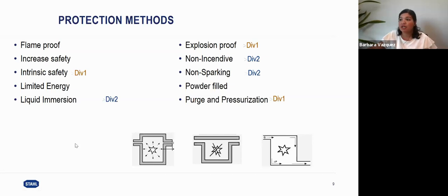For Division 2, liquid immersion, non-incendive, non-sparking. For Zone 0, we have intrinsic safety. For Zone 1, we have flame proof, increased safety, liquid immersion, powder fill. And for Zone 2, we have limited energy. So you can see all these, and there are more protection methods. These are just examples of some of the protection methods that we typically see. And you can see that it is important to know, again, where you want to install that item, because you need to make sure that the hazardous rating or the protection method being used is recognized for that specific area.